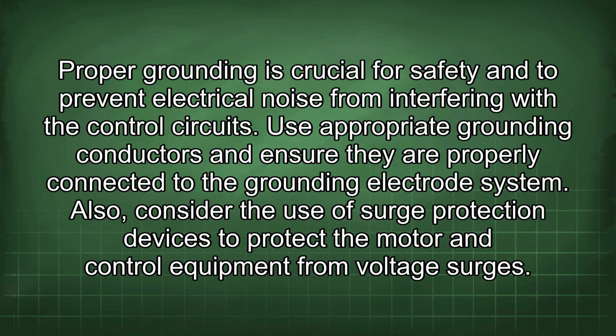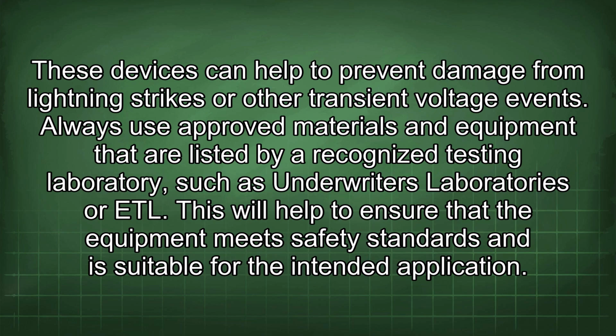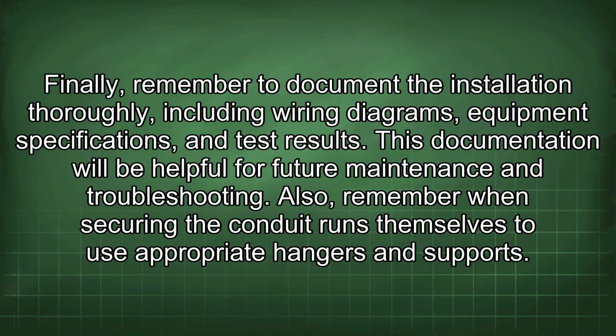Also, consider the use of surge protection devices to protect the motor and control equipment from voltage surges. These devices can help to prevent damage from lightning strikes or other transient voltage events. Always use approved materials and equipment that are listed by a recognized testing laboratory, such as Underwriters Laboratories or ETL. This will help to ensure that the equipment meets safety standards and is suitable for the intended application. Finally, remember to document the installation thoroughly, including wiring diagrams, equipment specifications, and test results. This documentation will be helpful for future maintenance and troubleshooting.